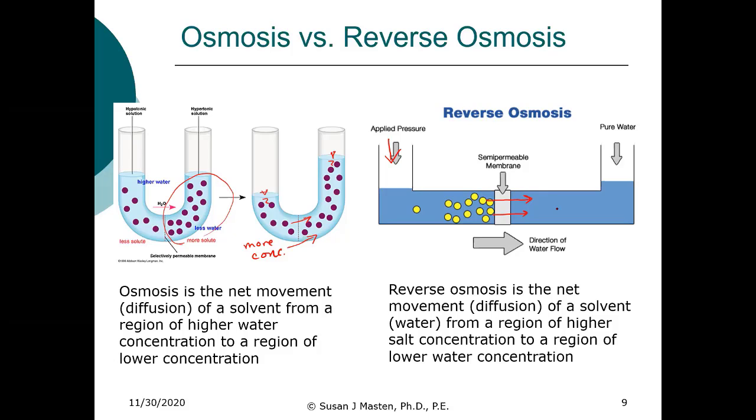This becomes our permeate. This is what we're producing. And then what doesn't pass through the membrane becomes our reject stream. So we have two streams that we start with one. We produce a permeate stream, and this is our product stream. And then we have a reject stream that has the higher concentration of whatever we're attempting to remove.